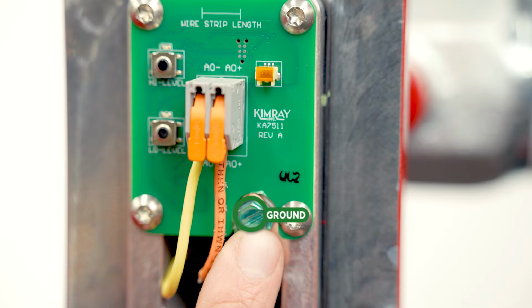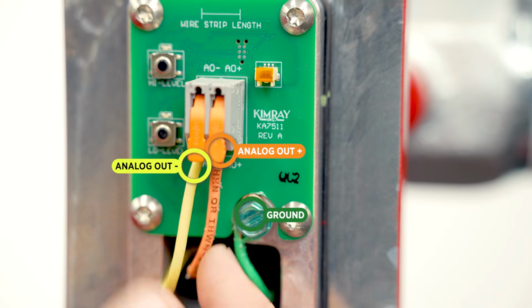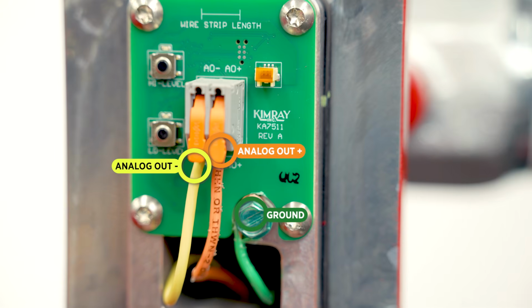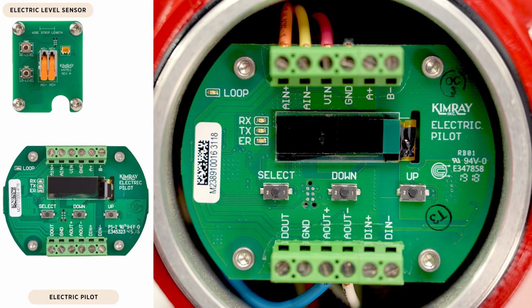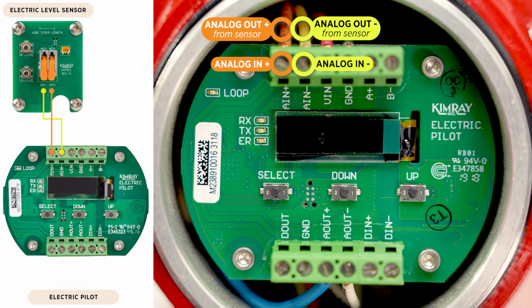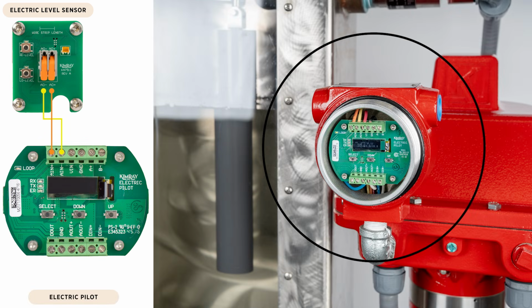Make sure your ground wire is connected and the analog out positive and negative wires are secure. Connect the analog out positive from the sensor to the analog in positive on the electric pilot and the analog out negative to the analog in negative. This electric level sensor output could also connect to a PLC or RTU. You can think of the pilot as a one-input PLC.